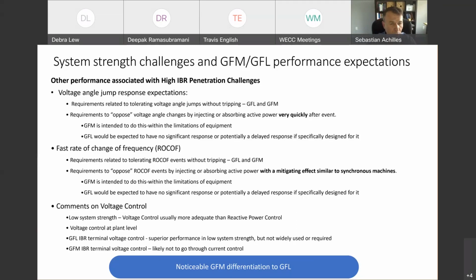Regarding voltage control, I want to make one comment related to the last 2 bullets. There are concepts of grid following inverter-based resources that perform terminal voltage control, and that has proven to be very beneficial in low system strength applications. Grid forming also does terminal voltage control, typically, that's the expectation, with the advantage that it doesn't do it through a current control.